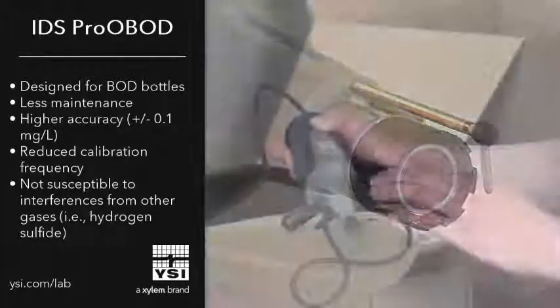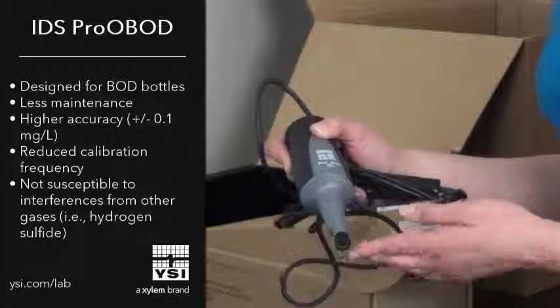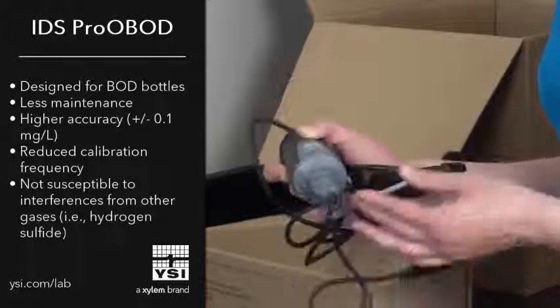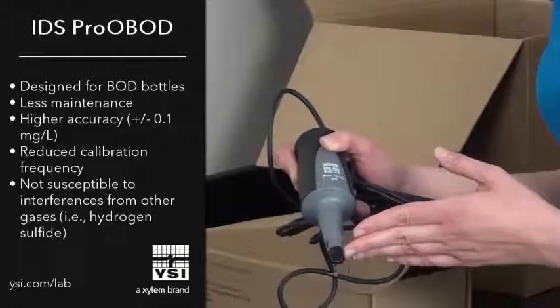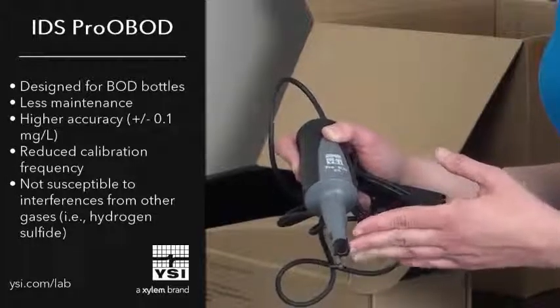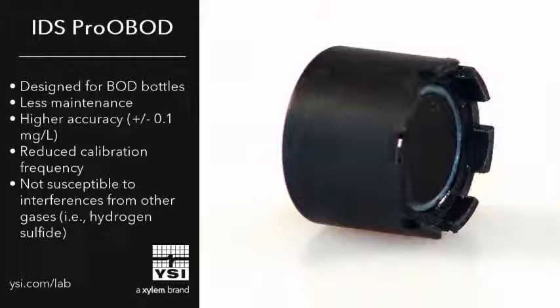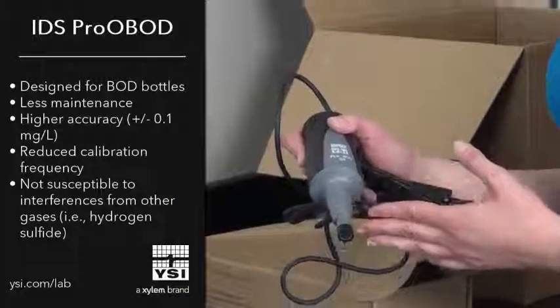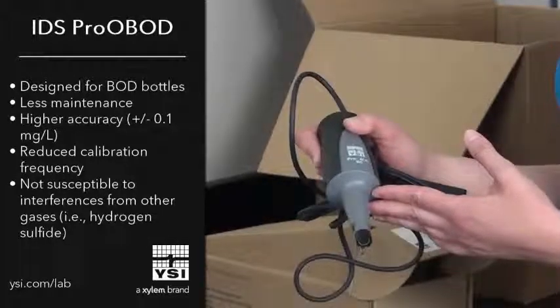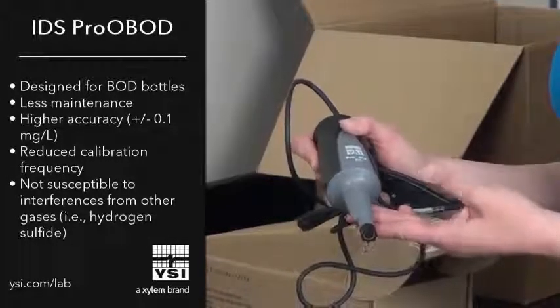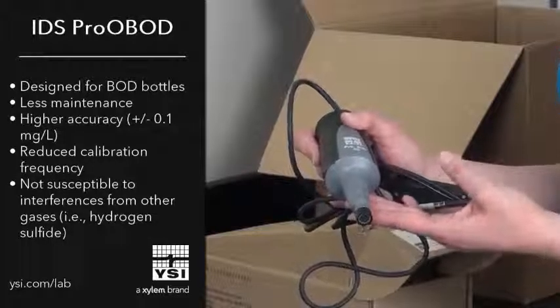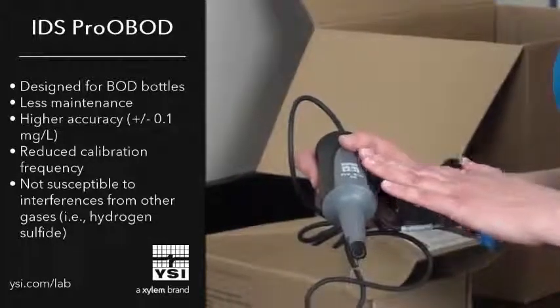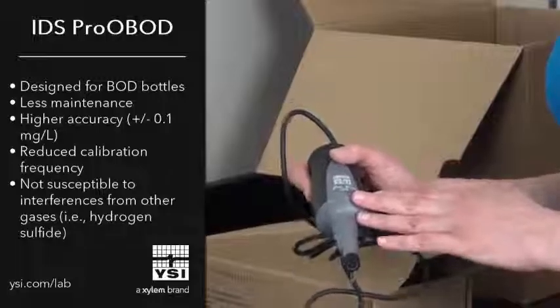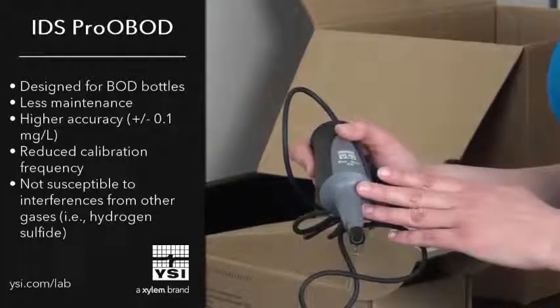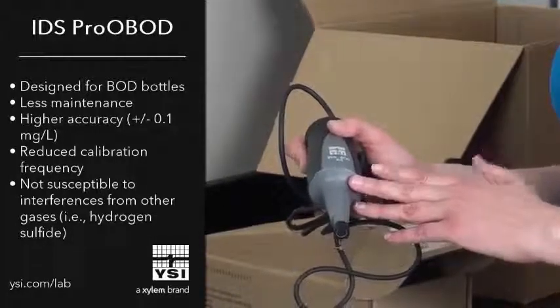A huge advantage of the optical-based technology is less maintenance, as this cap only needs to be replaced about once every 18 months. Additionally, it has a higher accuracy than membrane covered and is accurate to plus or minus 0.1 milligram per liter. Another major advantage of the optical-based technology is that it doesn't require as frequent calibrations and is not susceptible to interference from other gases that might be dissolved in your sample.